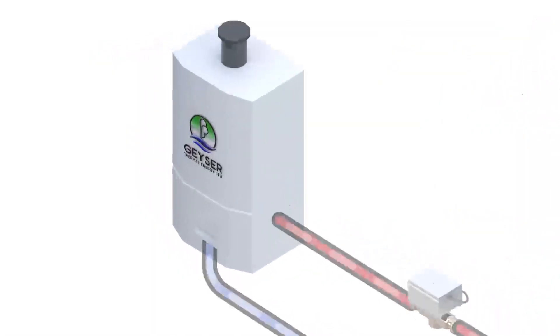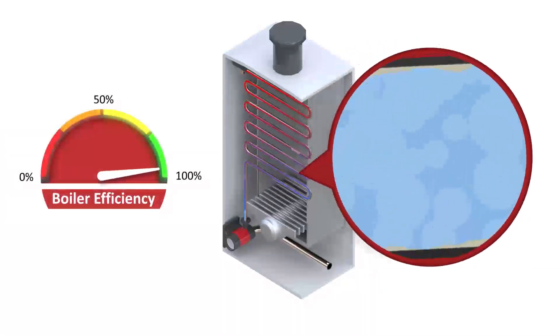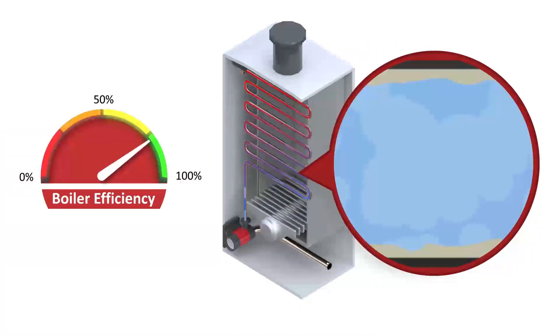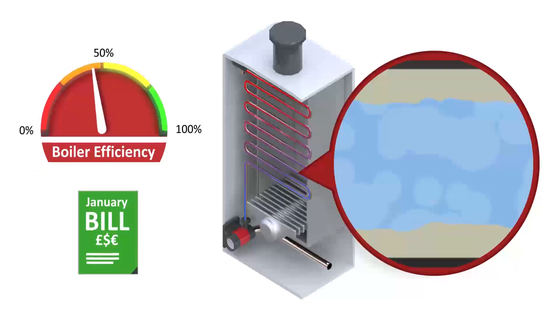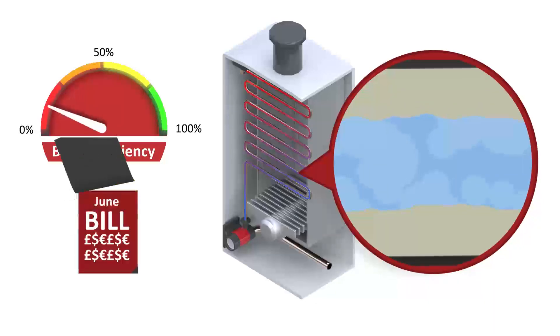A boiler has multiple components that are affected, including the heat exchanger, diverter valves and pumps. As scale builds up in a heat exchanger, the flow will reduce and its heat transfer capabilities will be diminished. This causes the output to be reduced and heating costs to rise until the boiler eventually fails.